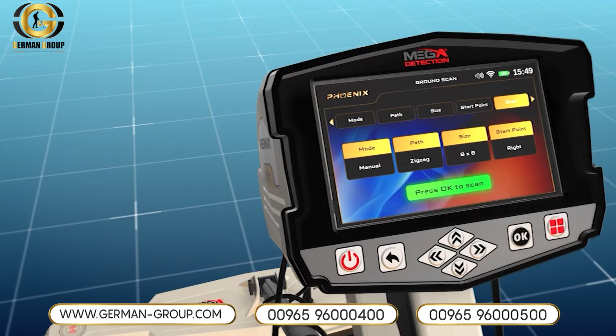Scan. After completing all the previous settings, the user will see a screen showing the settings chosen through the previous steps. You can press the button at the bottom of the screen. Press OK to scan, to actually start the scanning process. How to use. After the setup is complete, make sure the device is fully and correctly assembled. Hold the device in the following manner, and make sure that you're holding the device fixed to your body without moving. Then stand on the 0 or starting point in the scanning area and press the Start button, located under the handle of the device.